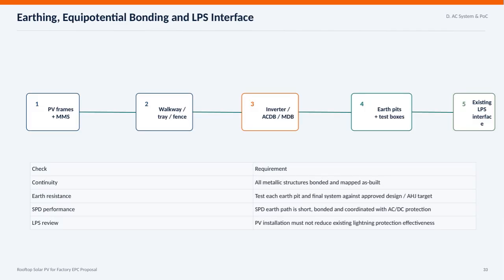On this slide, we focus on the critical aspects of earthing, equipotential bonding, and the lightning protection system interface specifically for the rooftop solar PV installation at the factory. First, you'll notice the key components involved, such as PV frames with mounting structures, walkways, inverters and distribution boards, earth pits with test boxes, and the existing lightning protection system interface.